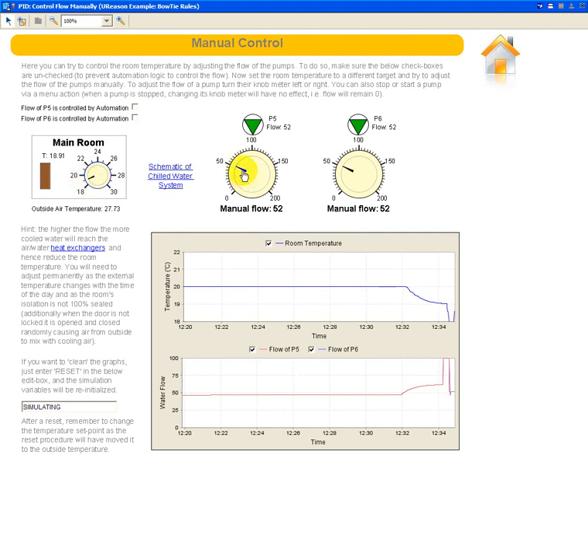So we can play with this here. It will be, of course, a permanent change, because we have here a door that can open and close and so on. So it can be quite tricky to adjust manually the temperature, but that's just the purpose of this exercise here. So let's maybe put this back in automatic mode so the PID can control the flow and regulate the temperature so that we have in a minute or two again 19 degrees into this room.